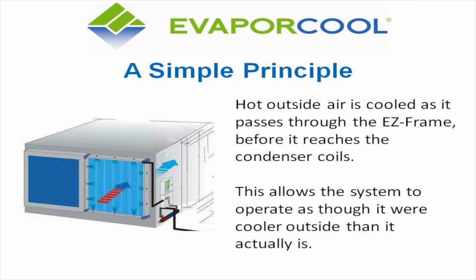And clearly, the principle is relatively simple now that you understand the components. As the outside air passes through our system, it's being flash evaporated through the control box, which understands what the temperature and humidity is. As the air comes in, you're going to see a temperature drop from outside air to going into the unit, so the unit's not working as hard. And I'm very much simplifying a lot of the mechanics of this, but we can get into more detail.